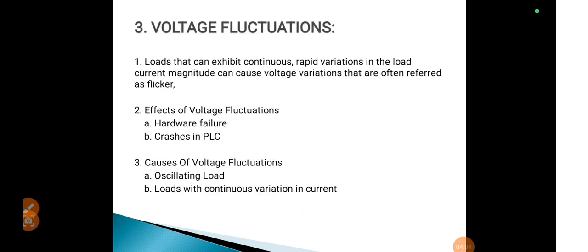The next power quality issue is voltage fluctuation. Voltage fluctuation means oscillation of the voltage amplitude by a signal with a frequency of 0 to 30 Hz. Voltage fluctuation occurs due to arc furnaces, frequent start or stop of electric motors, and oscillating loads. The effects of voltage fluctuations are mostly common to under voltage. The most notable consequence is the flickering of lighting and screens, giving the impression of unsteadiness of visual perception.